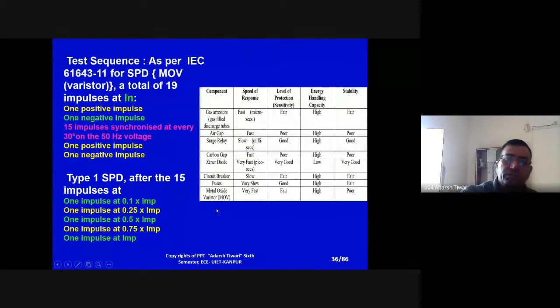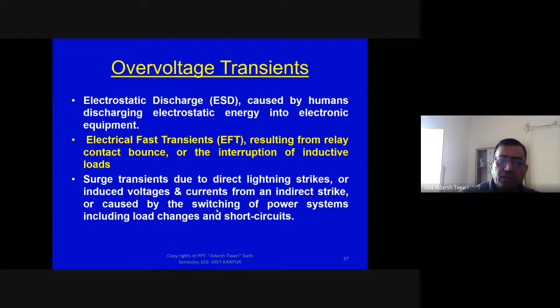So these are a few electronic components like gas filled discharge tube, air gap, surge relays, carbon gap, Zener diode, circuit breakers, fuse, and MOV, which is called metal oxide varistors. They are used for the surge protectors. Now, electrostatic discharge (ESD) caused by humans is also one of the effects which is very important while humans are working on the equipment for repair. ESD also imposes very high overvoltage transients, and it is so small, but the peak is so large, it will damage the sensitive electronics.